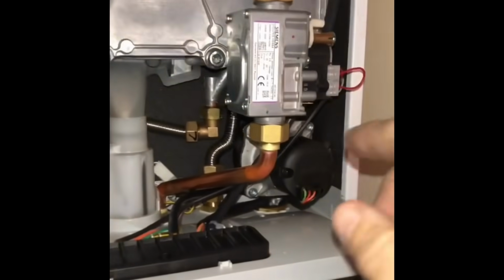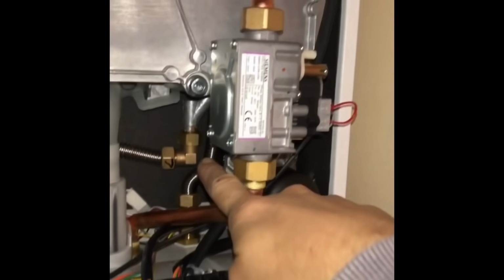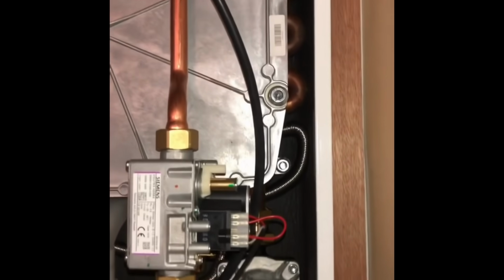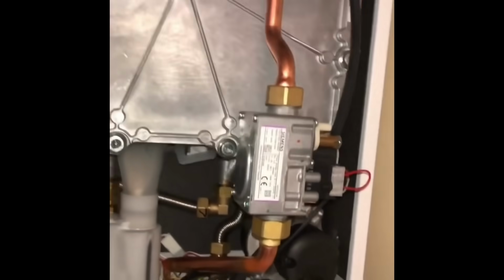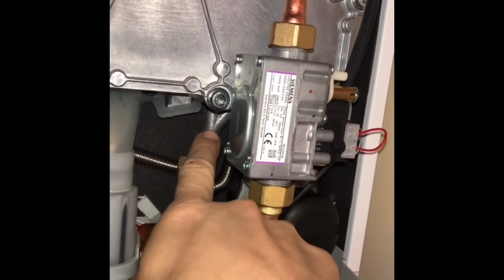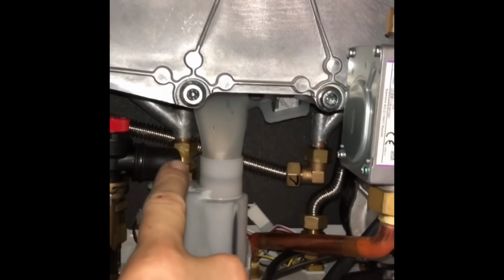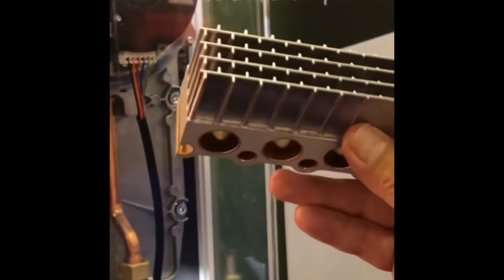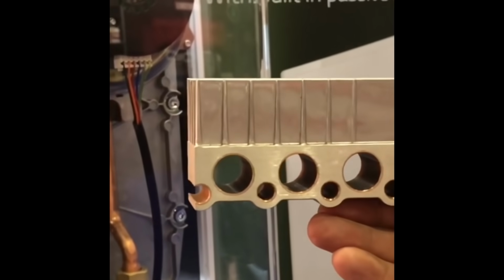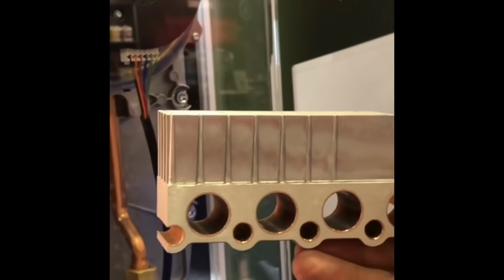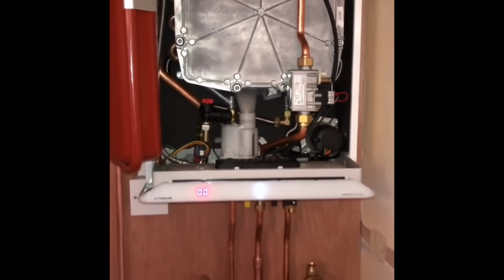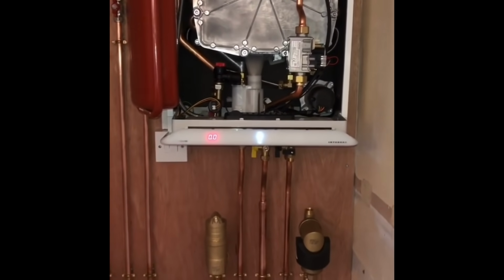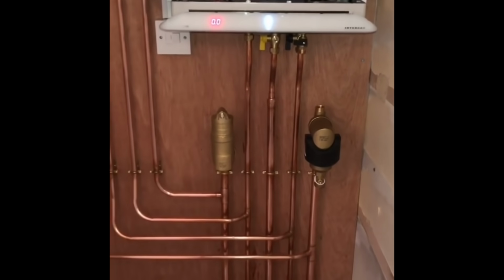So the cold water comes in, and on this model we've got flue gas heat recovery, so it goes up via this stainless steel pipe, gets preheated and enters the heat exchanger at the bottom there, passes through the heat exchanger, travels down and activates a flow switch. If we look at a cutout of the heat exchanger, we've got 22mm waterways for the central heating and independent 12mm waterways for the hot water. And because there's no plate or diverter valve, you can set this boiler up as a multi-point water heater, a system boiler or a combi.